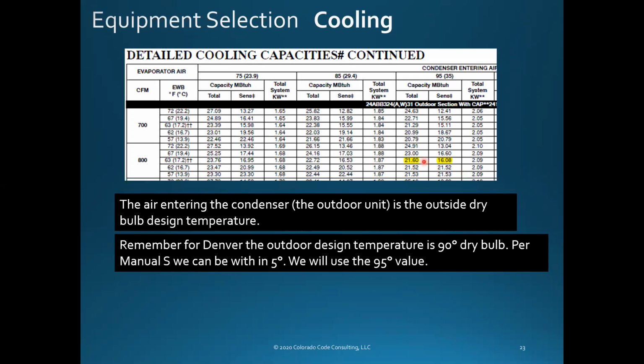So you got 21,600. If I took it down 10 degrees, now I'm at 22,720. And if I took it down another 10 degrees, I'm at 23,760. So I've dropped 2,000 BTU just because I'm up 20 degrees. This is important - you're looking at this stuff to make certain you're getting the capacity you need based on what your weather is where you're at.